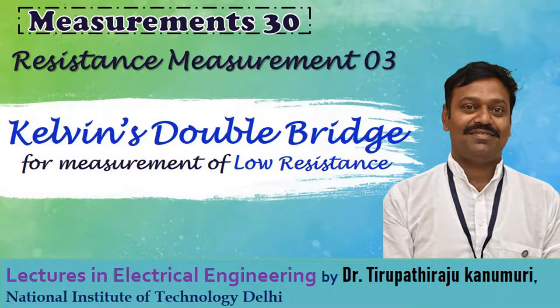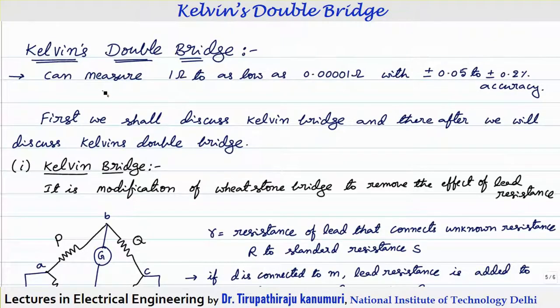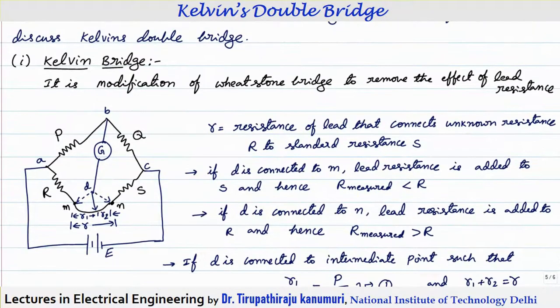Today we are going to discuss Kelvin's double bridge. This can be used to measure extremely low values of resistance, up to about 0.00001 ohms, with very high accuracy of 0.05 to 0.2 percentage. Before understanding the concept of the Kelvin double bridge, let us first discuss the Kelvin bridge, after which we will go for the Kelvin double bridge.